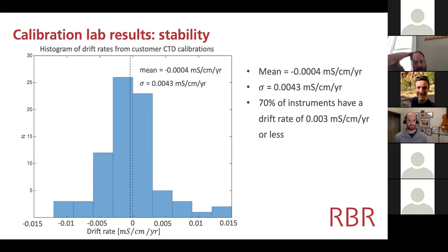So the first thing you notice is that the histogram here is effectively symmetric. The mean is about 0. So the drift of the inductive conductivity sensor is not a walk in one direction, it's a random walk. The second is that it's quite tightly centered. So 70% of these instruments are drifting at less than 3 milli-PSU per year, 70% of them. And the standard deviation, well, it's slightly higher than that, but it's the same kind of number. So this gives you a feel for what should be happening on instruments that are not necessarily taken care of in any way in particular.